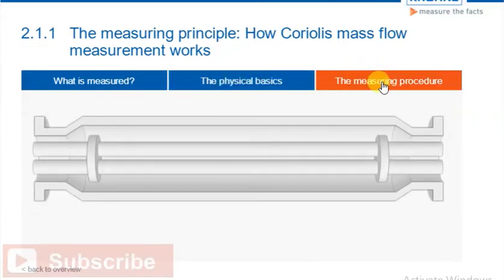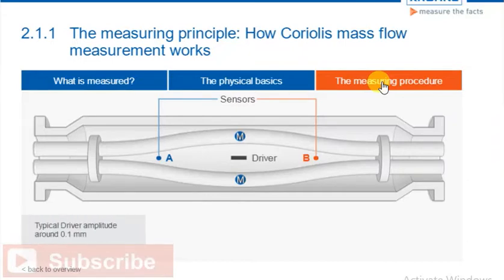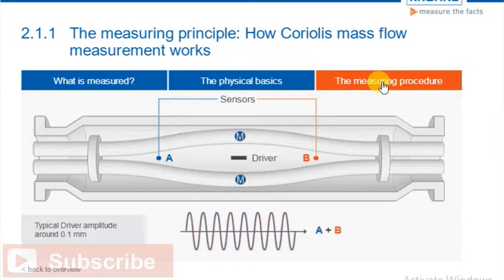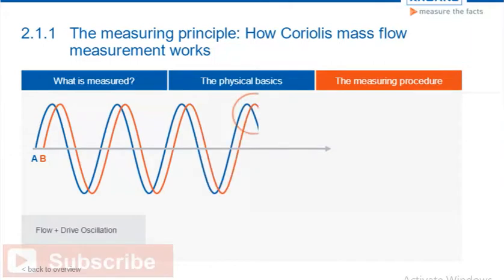In a twin-tube Coriolis meter, the driver resonates both tubes, and the sensors A and B measure deflections between the two tubes. In operation, the driver oscillates the tubes with a very small amplitude of around 0.1 mm. The amplitude is exaggerated in the diagrams to demonstrate the principle. The oscillation provides the angular velocity W required by the Coriolis principle. The driver oscillates the tubes at the resonant frequency of the system. This resonant frequency can be used to measure the process fluid density. When the flow starts, there is a time shift between the measurements at sensors A and B. This effect is caused by the deflection of the tube explained previously. The resulting time shift is proportional to the mass flow rate.